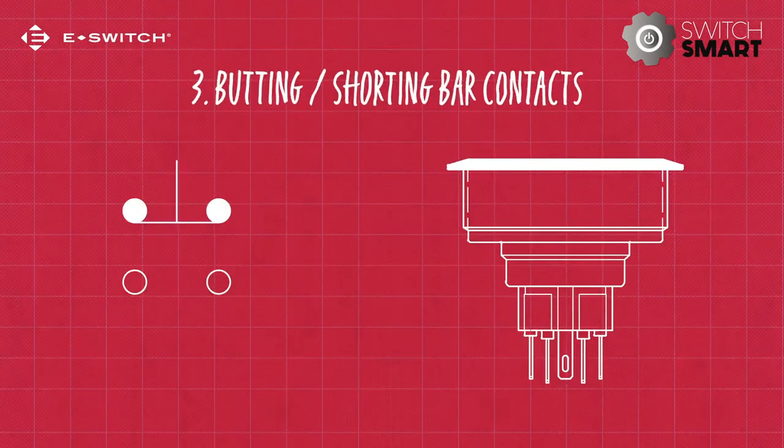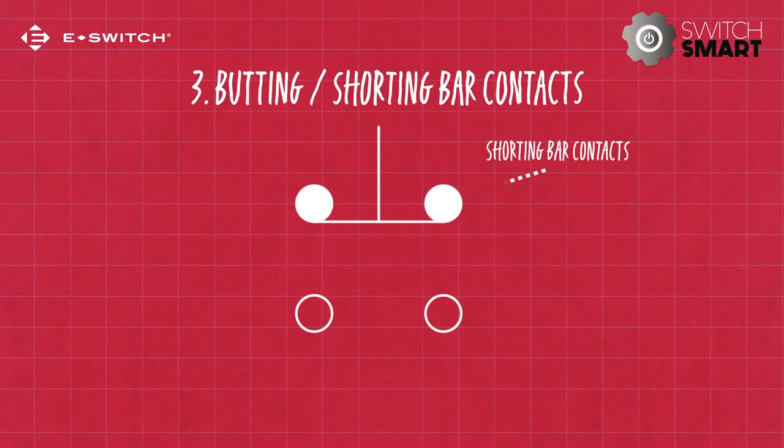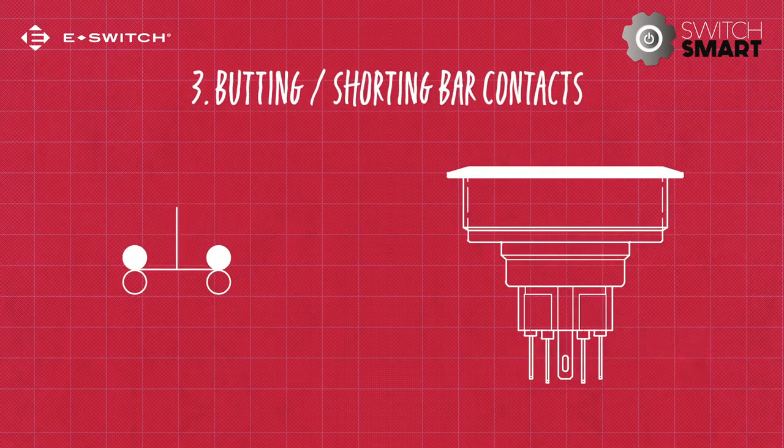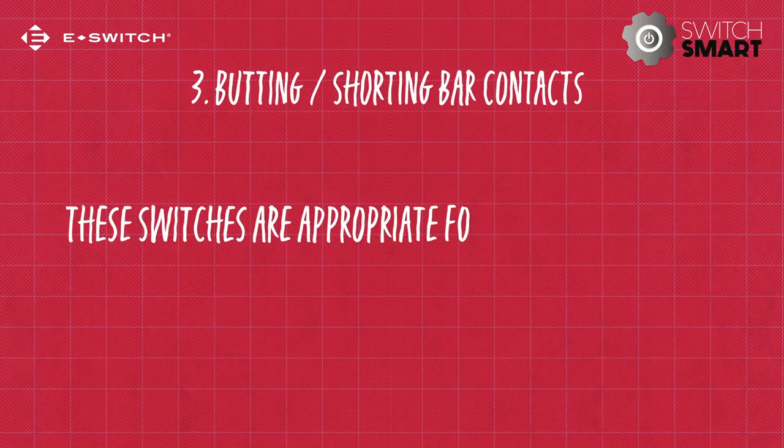This brings us to the final style of internal contact: butting contact, also known as a shorting bar style contact. Two contact points are connected via the shorting bar. When the actuator is pressed, the contact points butt up against the stationary contacts. The rapid rate of make and break means that these switches are appropriate for high current loads.